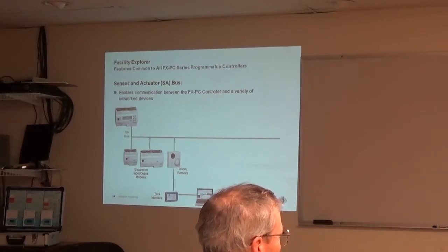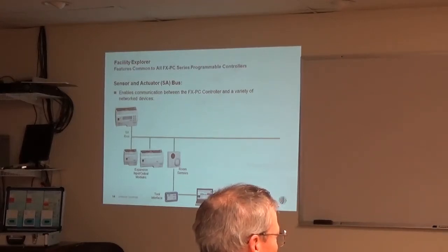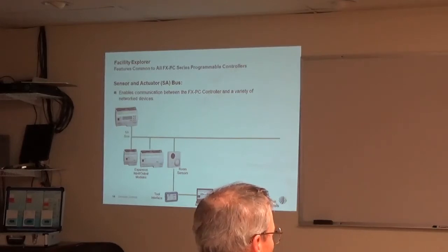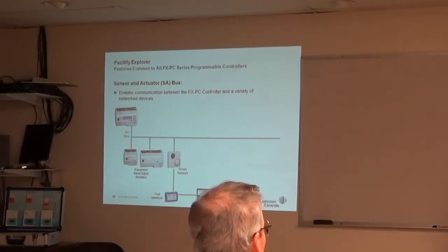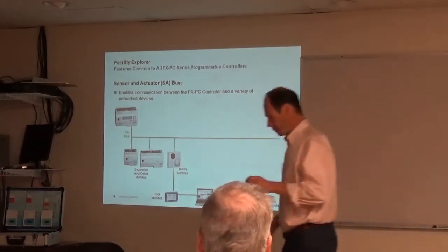So if you use the triac outputs, and also if you've got any of the rooftops, sometimes they've got a gas turn controller on for the igniter and all that stuff. Sometimes you might get a floating ground, so it's always better to isolate those triacs with a relay or something to keep that from feeding back, because that'll also mess you up sometimes when using the outputs.